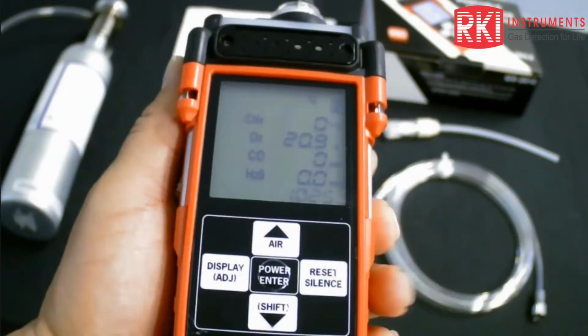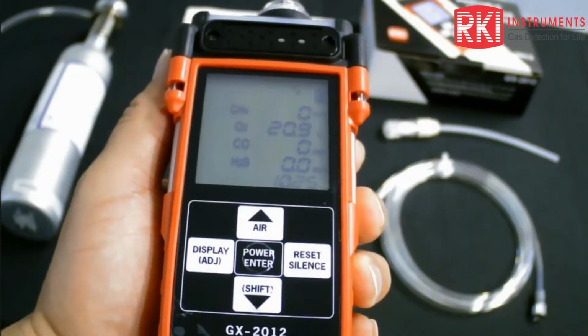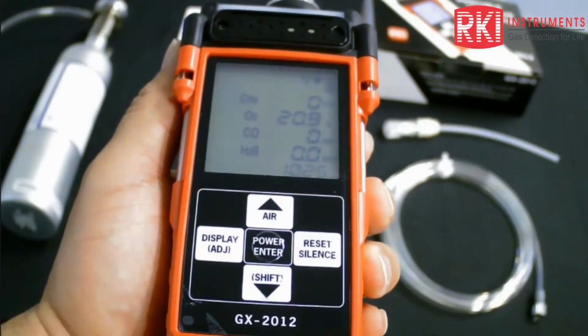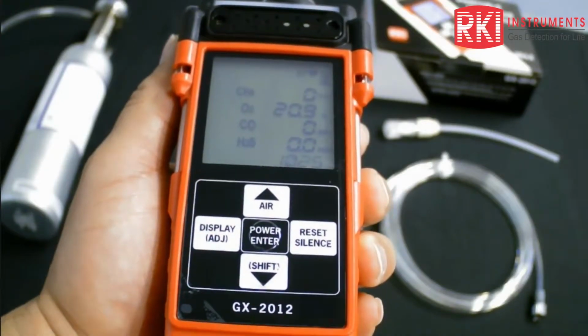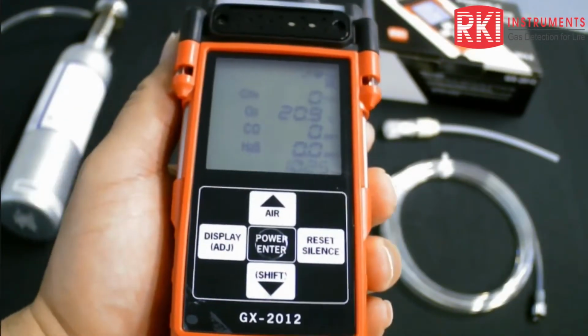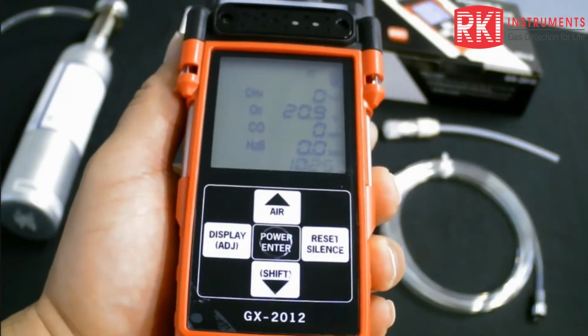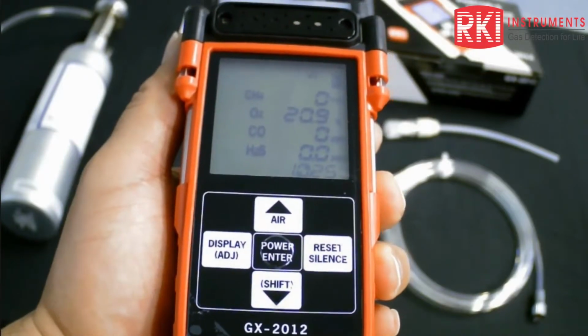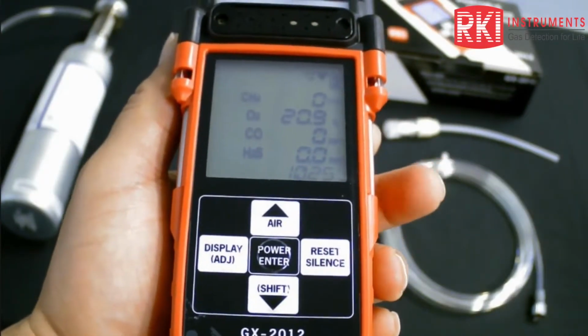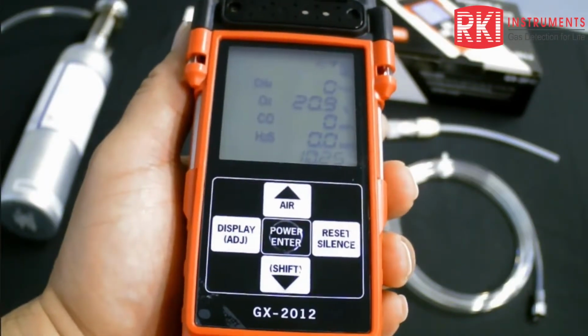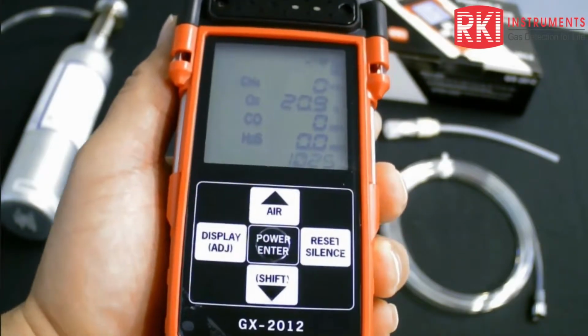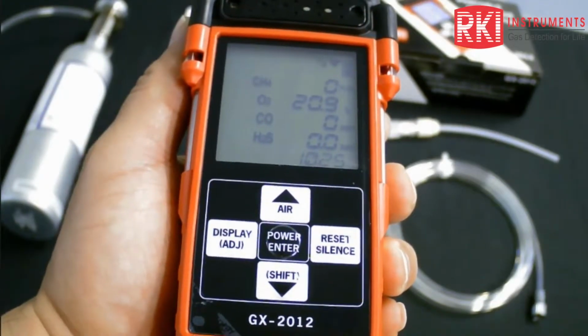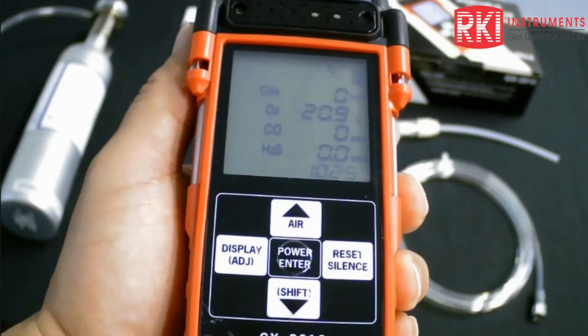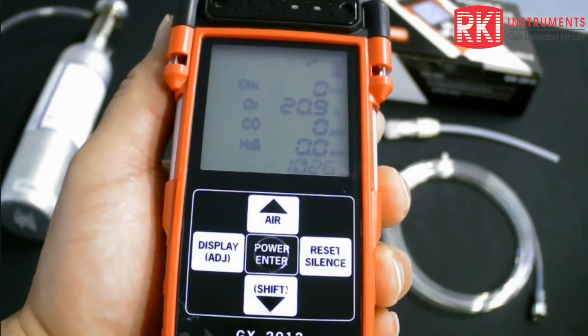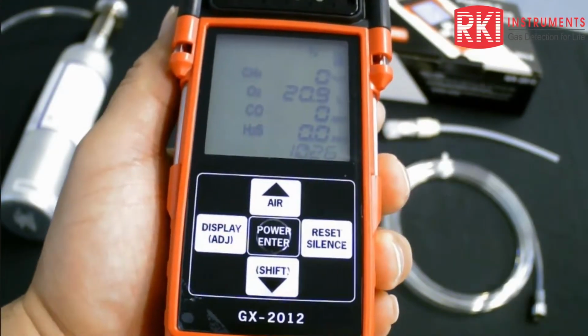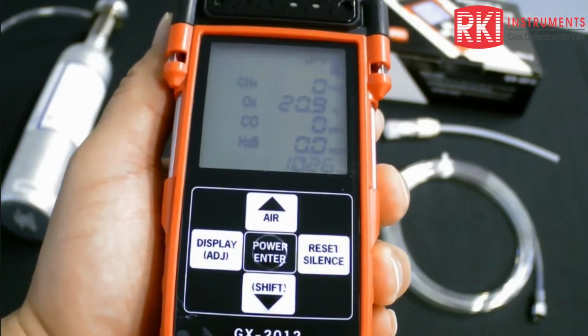Okay. So say you are in the volume range, and you take it out of the default and you make it volume. If there is 1% of LEL in the air, what would that reading be? That would be very low. It would be point something, because 1% by volume is 10,000 ppm basically. So again, 5% by volume is 100% LEL, right? So you would definitely want to be in the LEL range. So for methane, for example, 50% LEL is what we use as a cal gas to calibrate these to. That would be 2.5% by volume is 50% LEL.